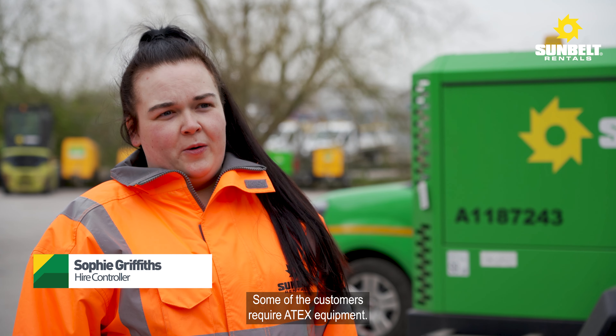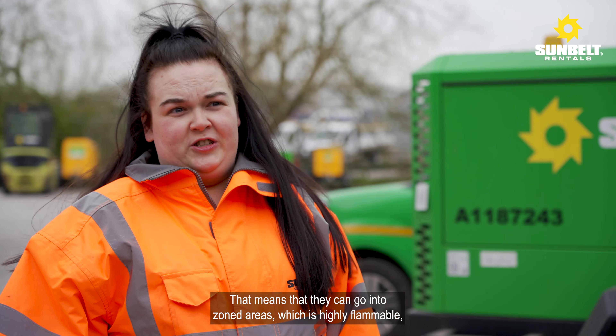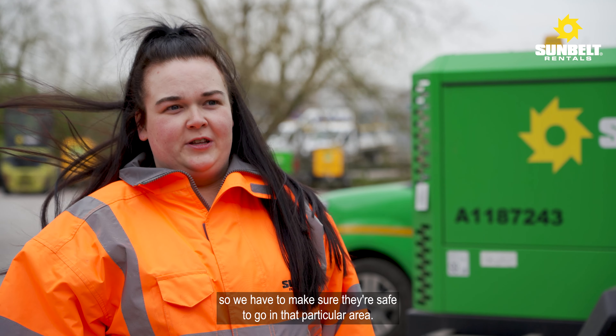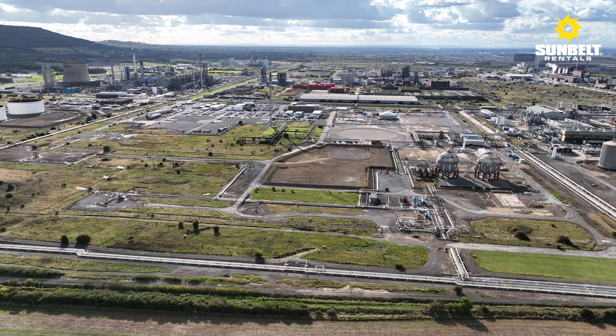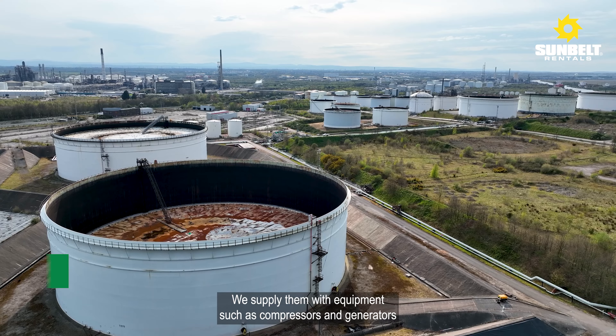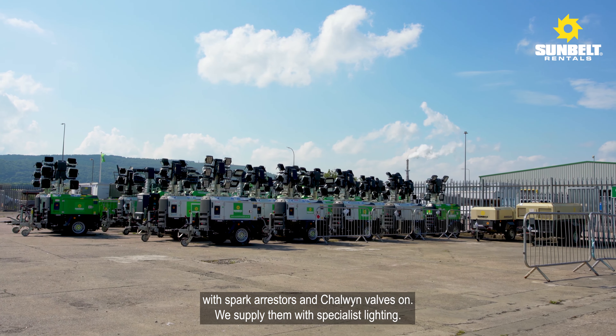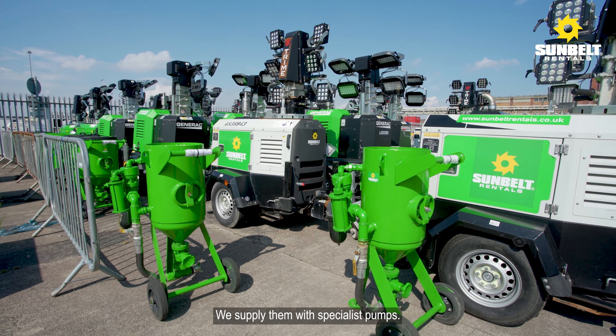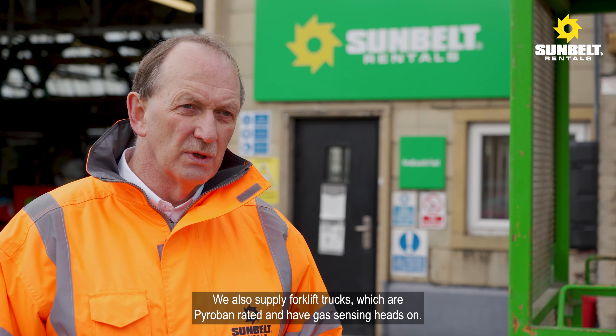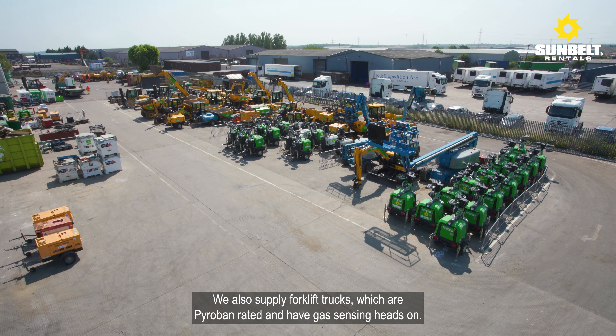Some customers require ATEX equipment, meaning it can go into zoned areas which are highly flammable, so we have to make sure it's safe for that particular area. We supply them with equipment such as compressors and generators with spark arresters and Chalwyn valves on, specialist lighting, specialist pumps, and also forklift trucks which are Pyroban rated and have gas sensing heads on.